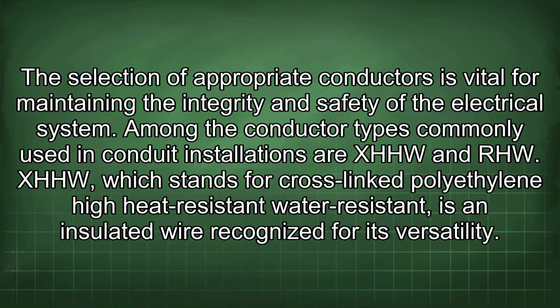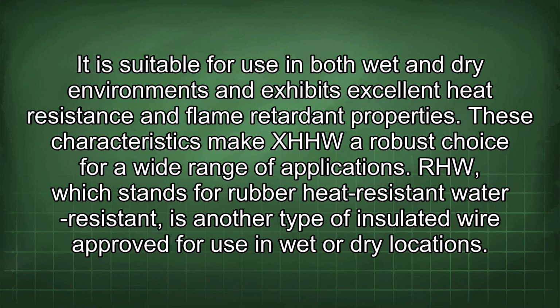Among the conductor types commonly used in conduit installations are XHHW and RHW. XHHW, which stands for cross-linked polyethylene high heat resistant water resistant, is an insulated wire recognized for its versatility. It is suitable for use in both wet and dry environments and exhibits excellent heat resistance and flame retardant properties. These characteristics make XHHW a robust choice for a wide range of applications.